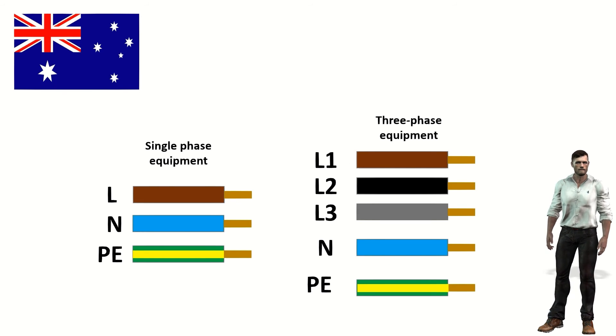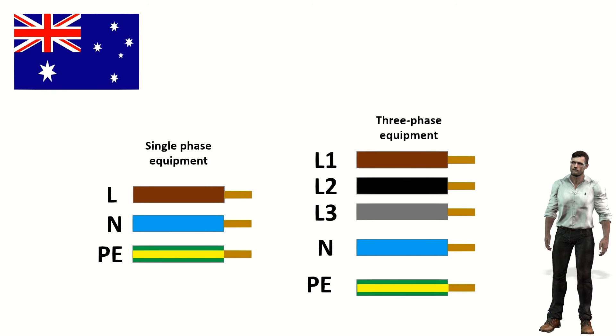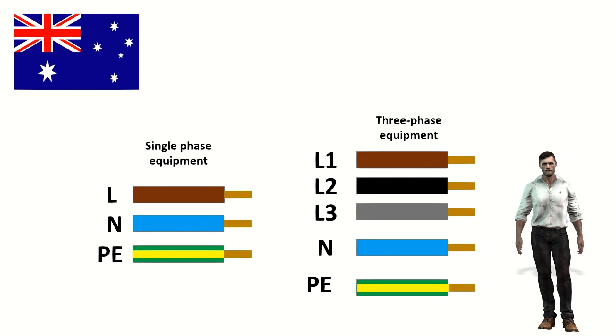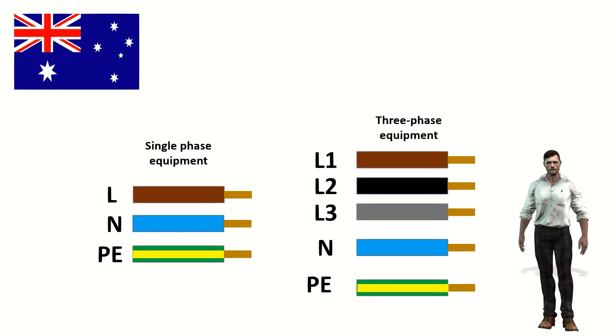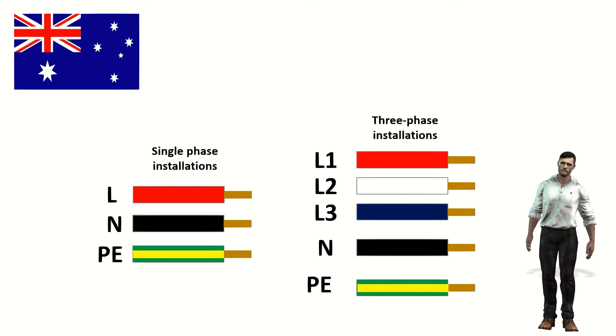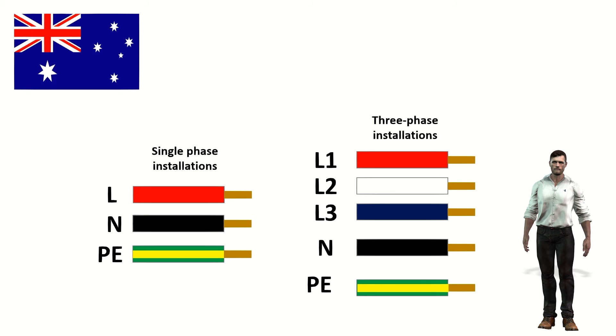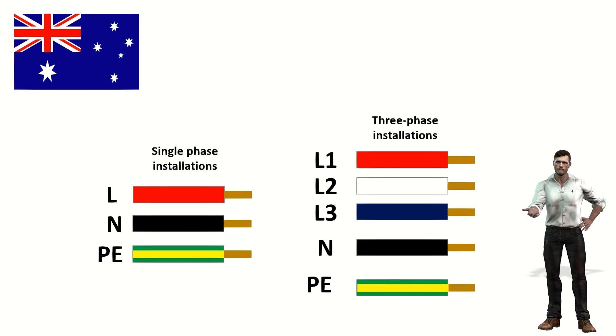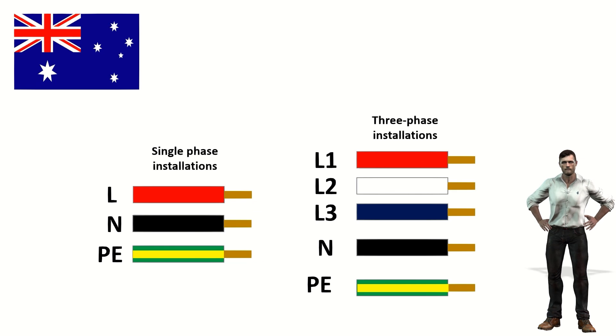Two color codes coexist in Australia: one for equipment cabling and one for facility cabling. The coding for equipment wiring follows the international IEC standard, using brown and blue for single-phase equipment for the phase and neutral wire respectively. In three-phase equipment the colors brown, black and gray are used for the phases and blue for the neutral. The ground wire is green with a yellow stripe. For installations in buildings, another coding is used: red for the phase cable and black for the neutral cable in single-phase installations. For three-phase installations: red for phase one, white for phase two and dark blue for phase three. The neutral is black, and the protective earth wire is green with a yellow stripe.